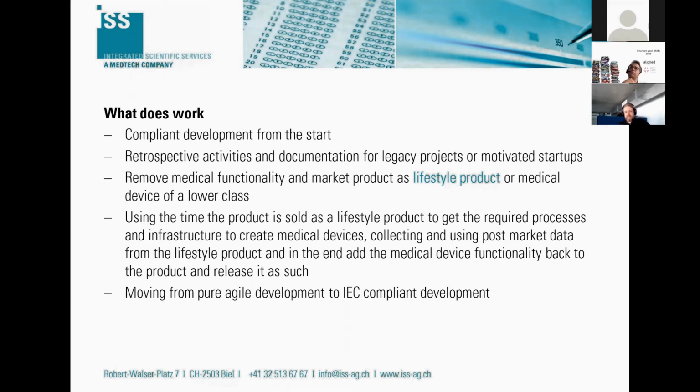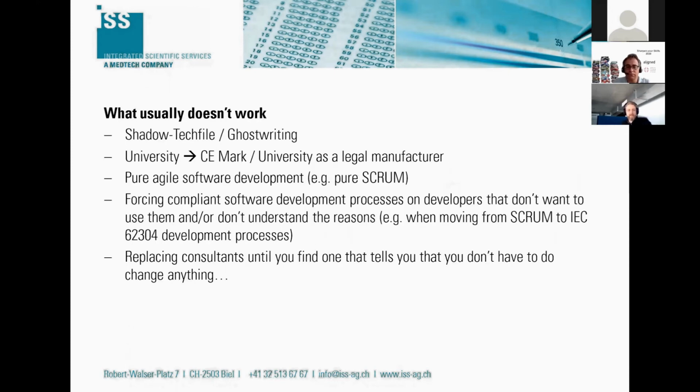And if it sells, you can use the time and money to get up to spec with regulated software development and add the medical functionality back afterwards, and release it later as a medical product. What also works, that's encouraging for many startups, is you can move from pure agile development to IEC compliant development.